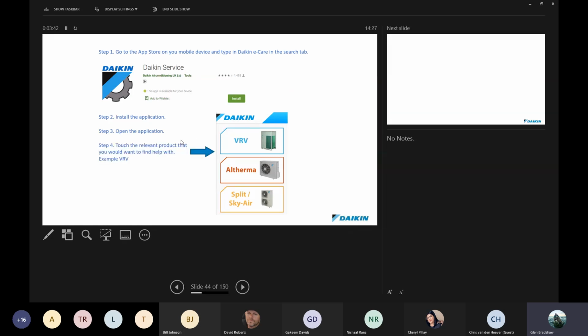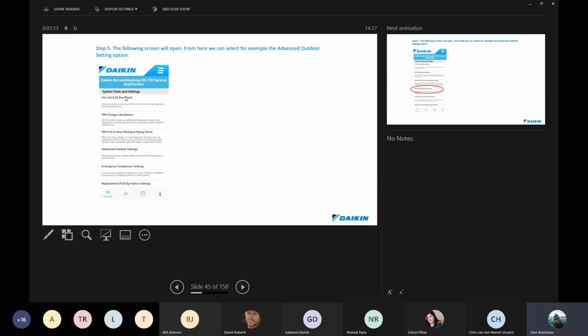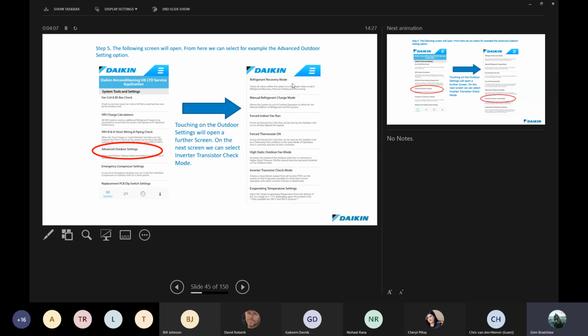Okay, so let's go back there. Basically, once you've installed the application, you open it. You've got three options. You can choose VRV, or Altherma, or Split and Sky Air. Then you can go in there and it'll give you a menu, from which you can choose what you want to look at. Here we're looking at advanced outdoor settings. That takes you into things like the refrigerant recovery mode, which you're going to use for putting a vacuum in for recovering refrigerant, and manual refrigerant charge mode, forcing the indoor units on, forcing the thermostat on.